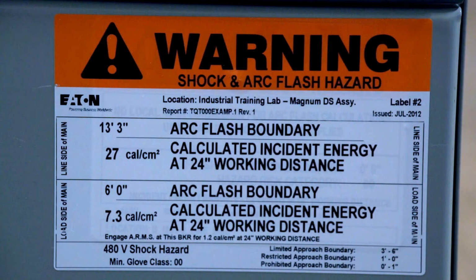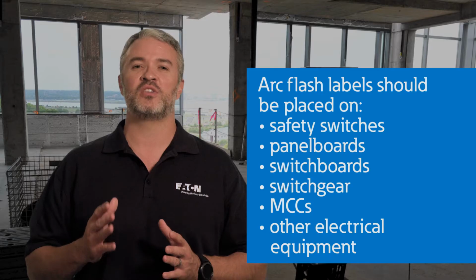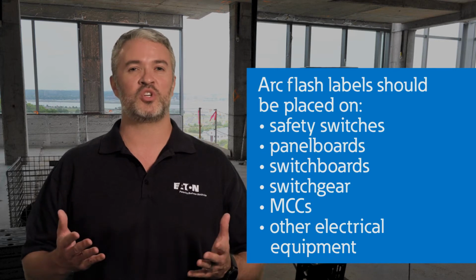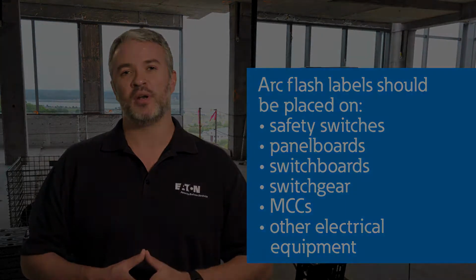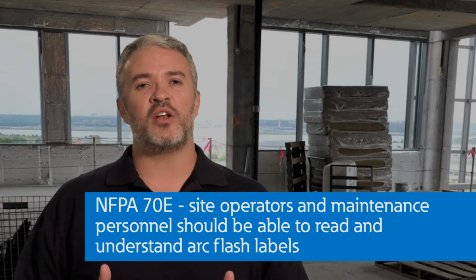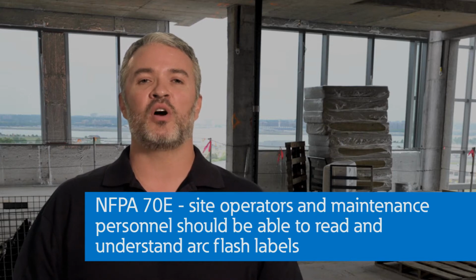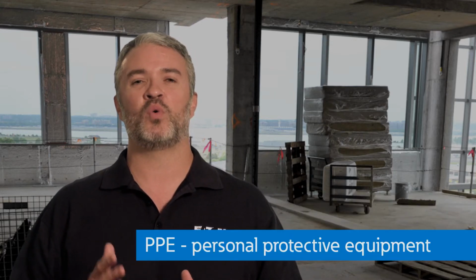Arc flash labels indicating the incident energy level and the arc flash boundary are affixed on safety switches, panel boards, switchboards, switchgear, MCCs, and other pieces of electrical equipment. As a field electrician, the primary thing that we look for off of the arc flash label is the boundary area, to make sure that we set up the right sized perimeter to keep out anybody that does not absolutely have to be in that vicinity. As part of NFPA 70E, site operators and maintenance personnel should be trained on how to read arc flash labels and understand the proper personal protective equipment, or PPE, required when working inside the arc flash boundary.